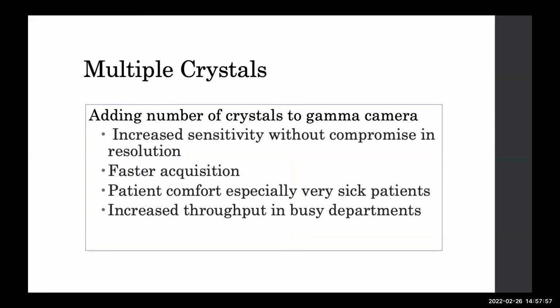What is the advantage of having multiple crystals in the camera? Adding crystals to the camera increases the sensitivity without compromising the resolution. So the more heads you have, the more the sensitivity of the camera increases. There's also faster acquisition. If you have a dual head camera, you can take the anterior image and posterior image of a patient simultaneously. You can take both lateral images simultaneously. So this is faster acquisition time. You save time, and for a very sick patient, it becomes very comfortable. Within a few minutes you finish a scan which would have taken half an hour to 40 minutes.